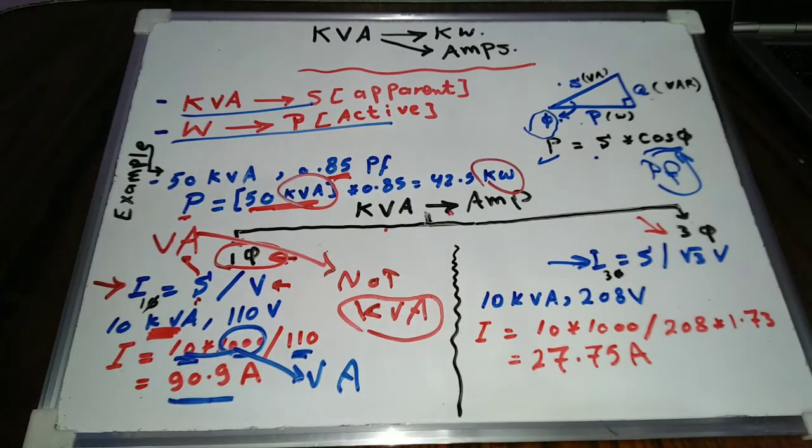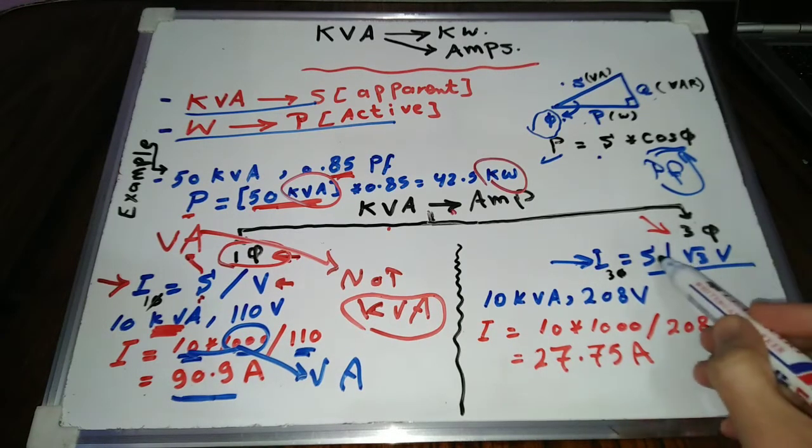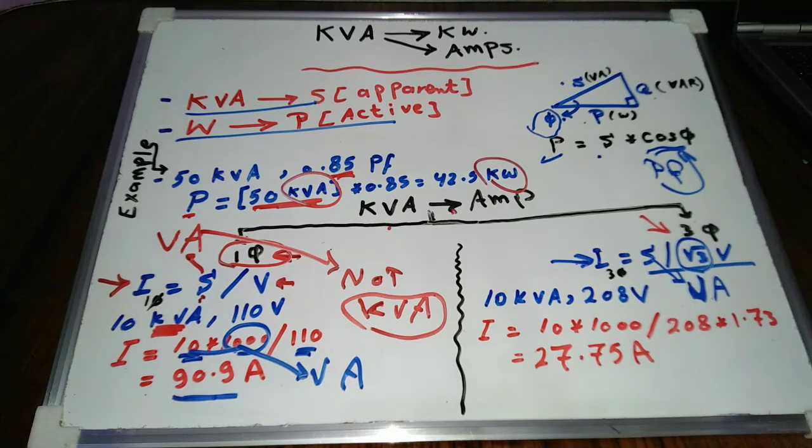Current I equals apparent power S in volt ampere, divided by voltage in volt multiplied by 1.73. It's clear that the two equations are similar except in case of three phase we multiply voltage by 1.73.